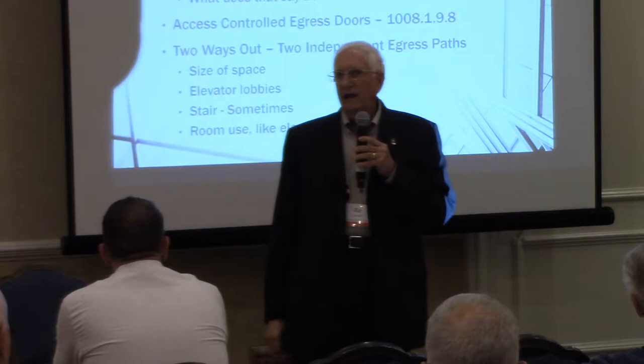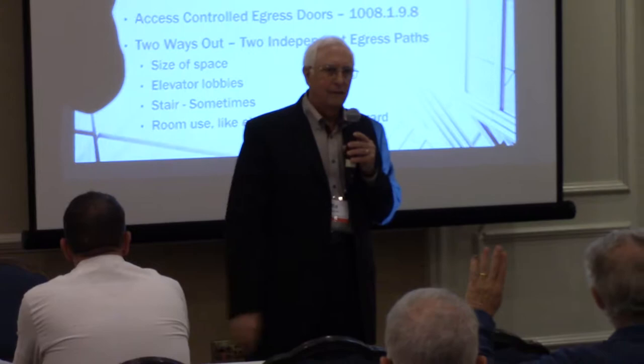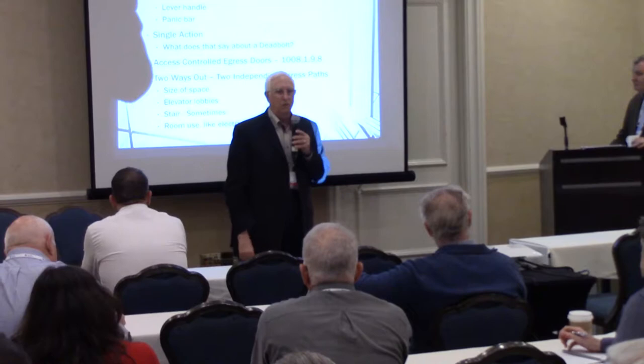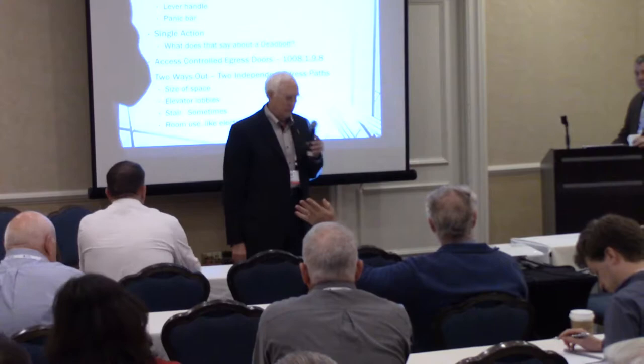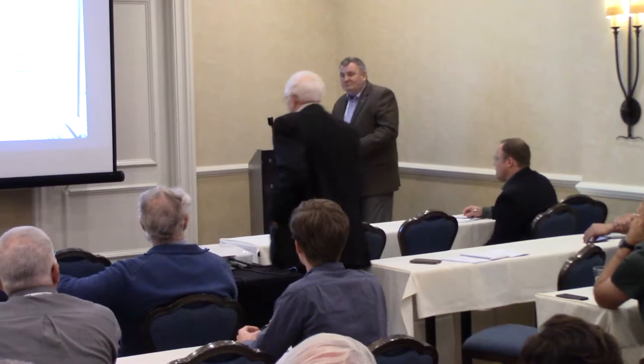A lot of people say at night there aren't many people here, so I can hard-lock that door. No, you can't. The code is not respectful of time. It is respectful of the number of people — all code relates to occupancy numbers. But for a deadbolt, you can't put it on the door. You can't have a different operation at night just because you have low occupancy.